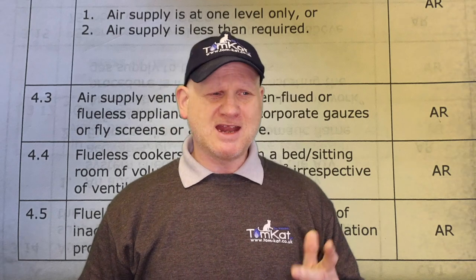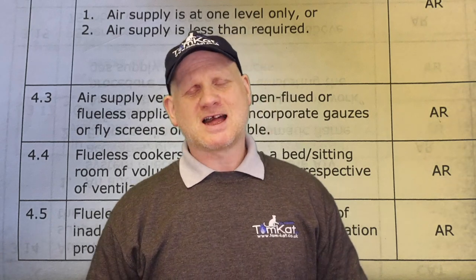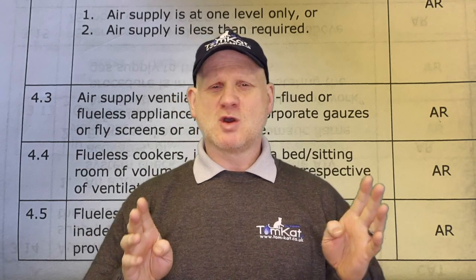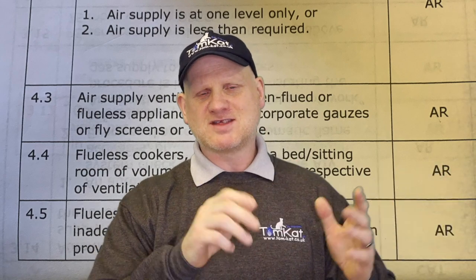So when you go out to a cooker that hasn't got ventilation, do we at-risk it or not? According to IGEM G11 unsafe situations, anything to do with ventilation is classed as at-risk if it's not there. If a kitchen is between 0 and 5 metres cubed with no ventilation requiring 100 cm², it's at-risk. Between 5 and 10 requiring 50 cm² with no ventilation — at-risk. If there's no ventilation at all or the room is undersized, it's at-risk, even if it's a bedsit.